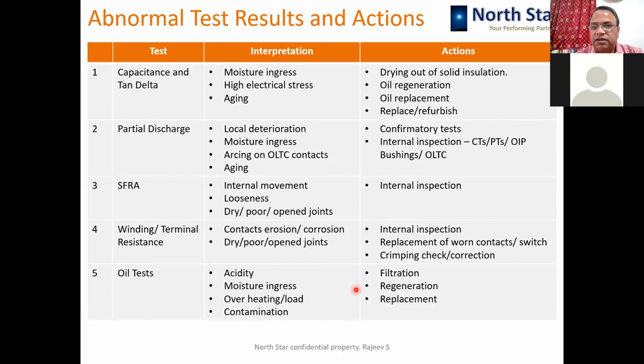Oil test results: acidity could be high, moisture ingress in the oil, overheating because of load or the temperature, and contamination. So the action could be filtration, regeneration. If both are not working, then replacement of the oil.